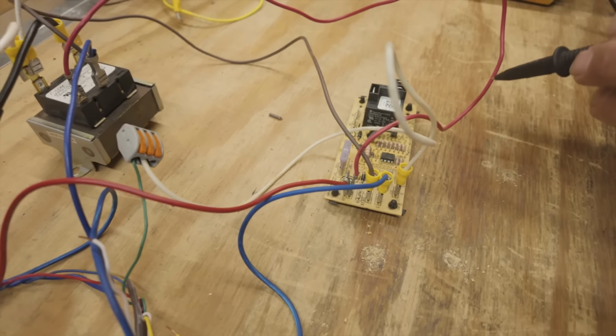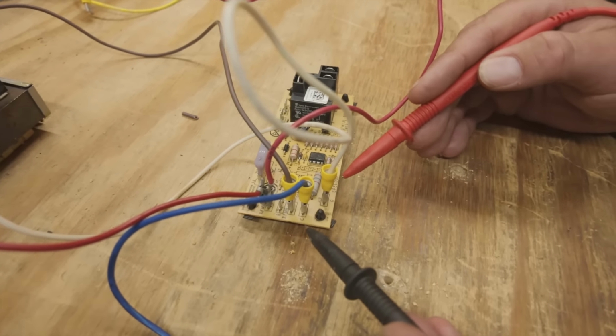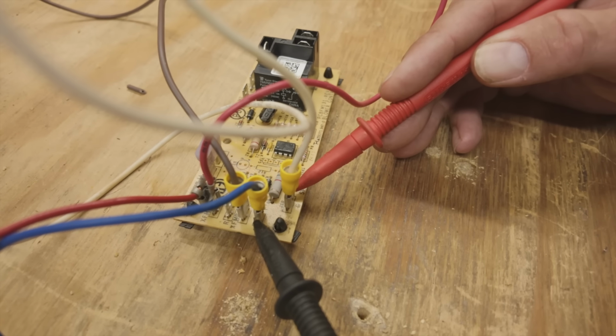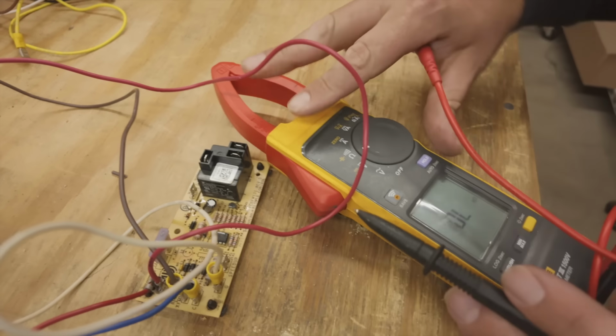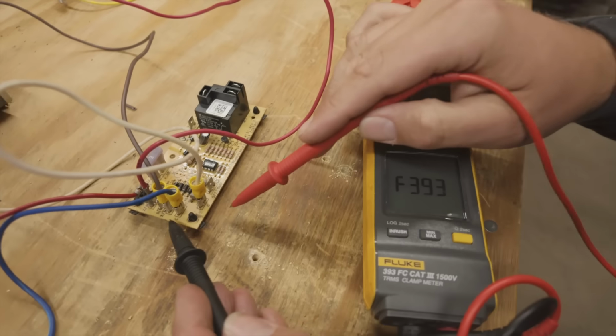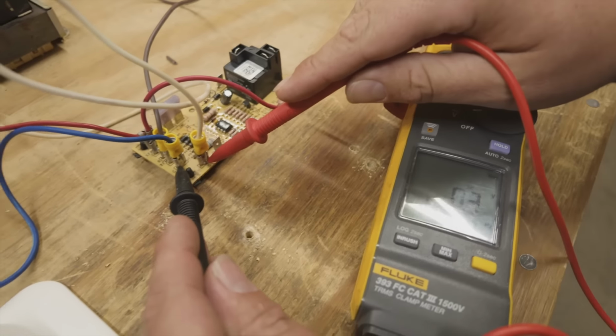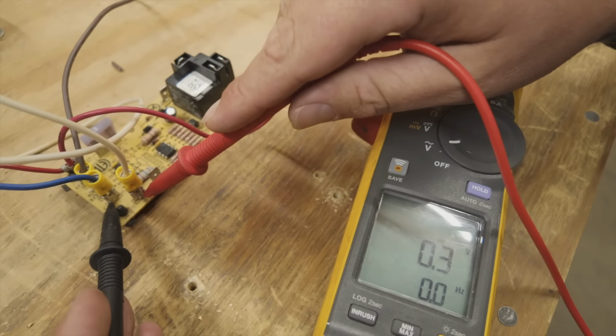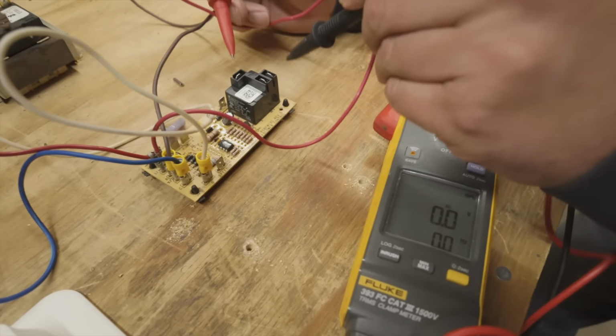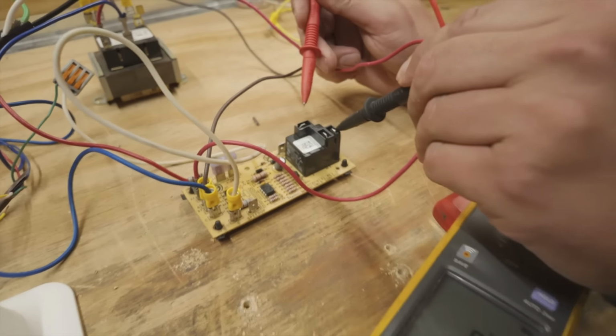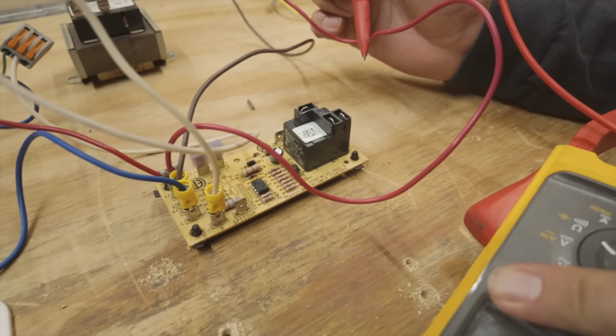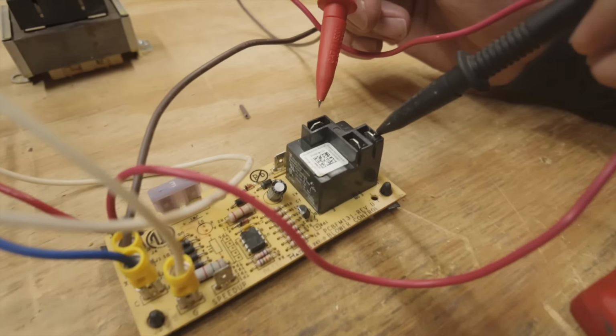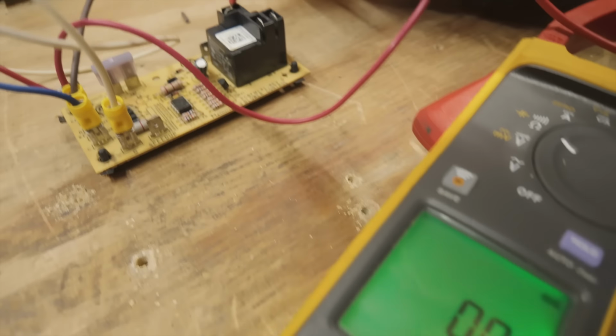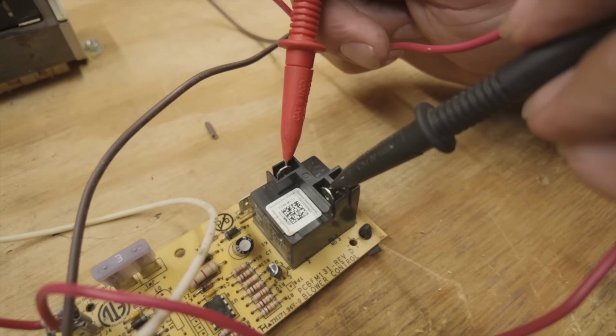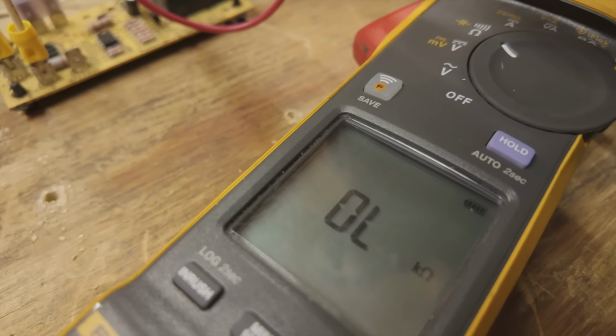Now, for the relay portion, right now we don't have a call, okay? How do we know that? If we go from G to C, you can see on our meter, let's put it on volts AC and go from C to G. 0, right? So we don't have a call. So let's look at what types of contacts we have. So from here to here, oh, we got to go to continuity. From here to here, we've got a normally closed contact. And then from here to here, we've got a normally open contact.